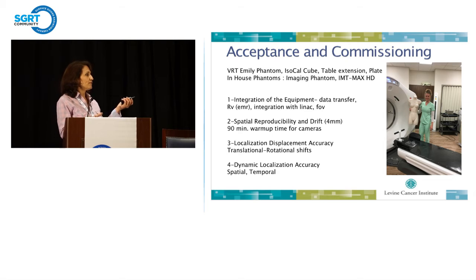For localization and displacement accuracy, you set an isocenter, you move from the isocenter by like 5 centimeters, 1 centimeter, 1 millimeter, and check whether you actually move that much. And you prove that with your MVs and KVs for your translational shifts. This task group also talks about how camera systems or infrared systems can drift, and it's not good to use them in the first 90 minutes. So you check on that.